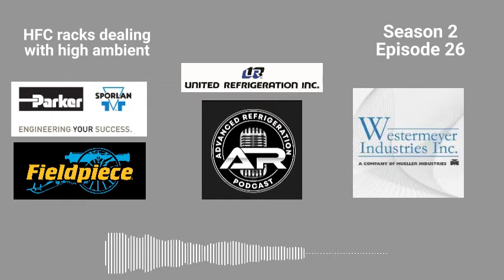Okay. Now let's talk about this. Mechanical rooms being hot. Making sure exhaust fans are working in mechanical rooms. That's a huge thing. Insulation on the pipes. It's as easy as just putting insulation on the pipes. That's one of the biggest things that gets let go that actually does help with sizing of condenser. I mean, if you're bringing back 20-degree cool suction gas, but yet the motor room's 140 degrees and you basically have no insulation, it's the equivalent of probably putting 50-degree suction gas back into that compressor. So it's just going to kill your discharge temperatures. It's all hell.